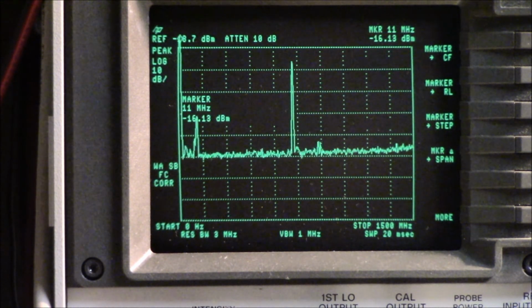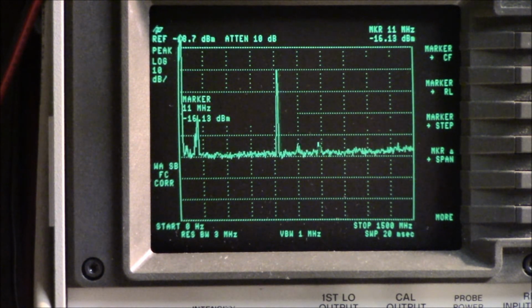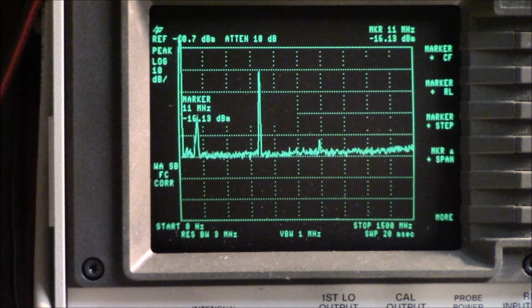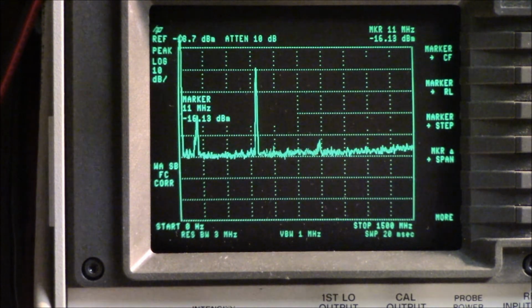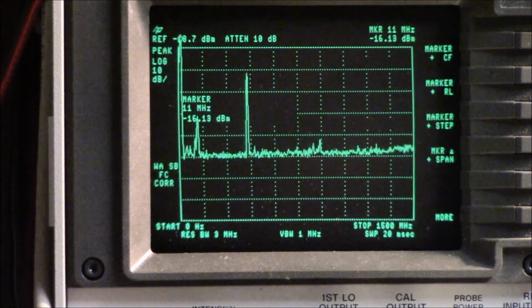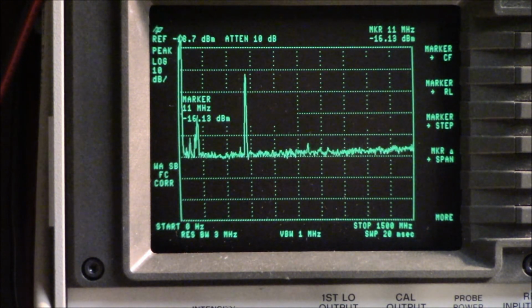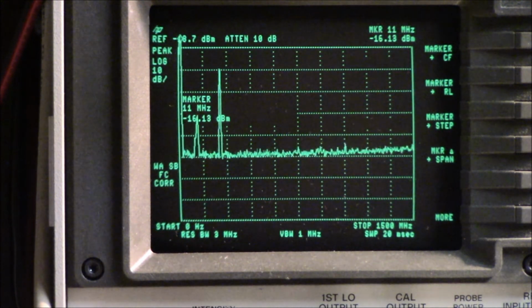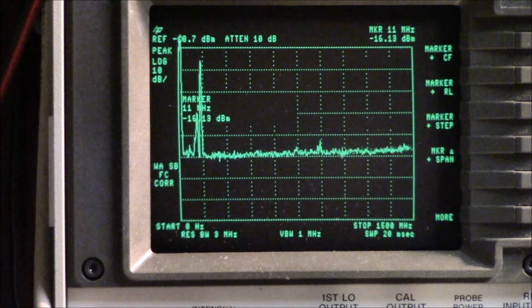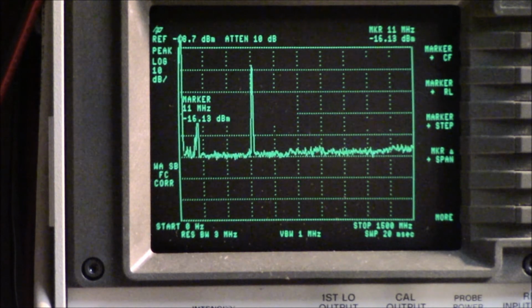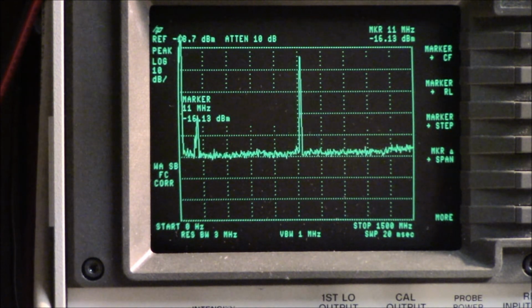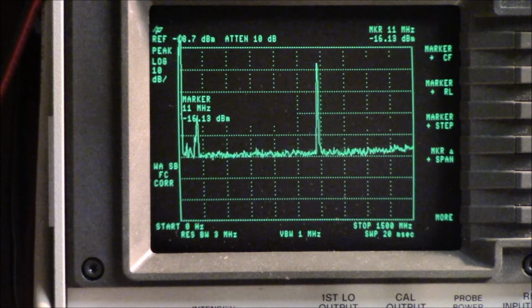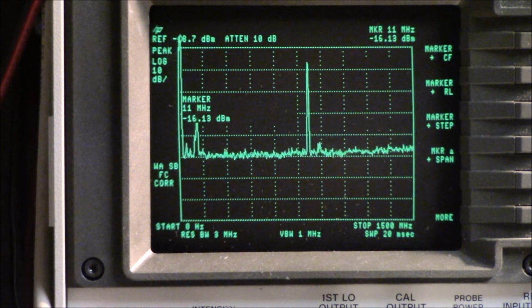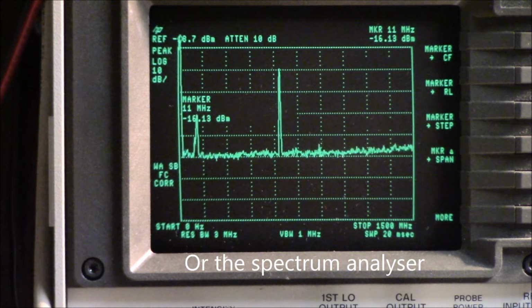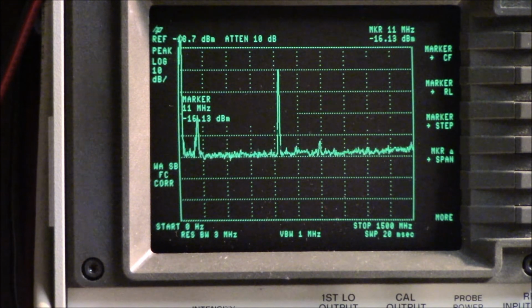So right now I'm at 710 megahertz. There it drops again. See, right there is 610 megahertz. And it drops again. 510 megahertz. 410 megahertz it dropped. So it's every 100 megahertz I'm losing the strength of the signal. It seems like there might be something wrong with the signal generator. And I'm set at minus 20 dBm right now.